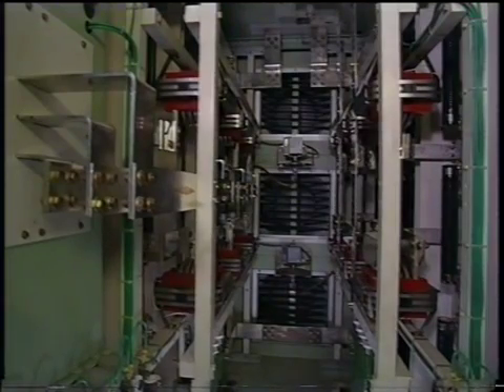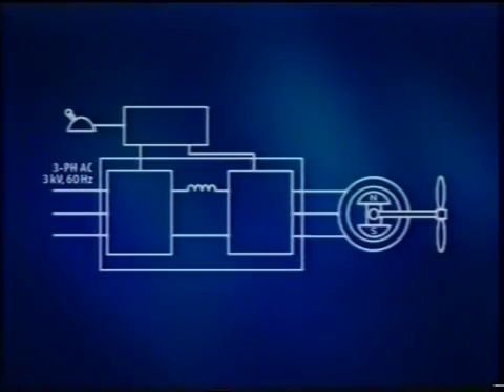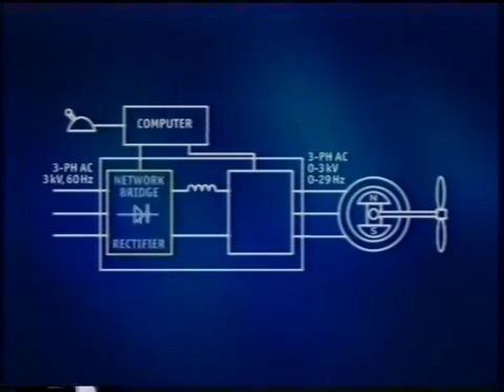This is a three-phase synchroconverter. It takes fixed frequency AC and under computer-controlled switching converts it to variable frequency AC and changes the motor voltage in proportion. The converter is in two identical sections: the network bridge, essentially the controlled rectification stage, and the machine bridge, the controlled inversion stage.